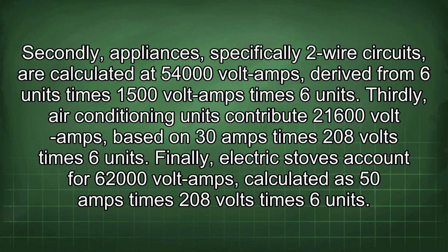Secondly, appliances, specifically two-wire circuits, are calculated at 54,000 volt amps, derived from 6 units times 1500 volt amps times 6 units. Thirdly, air conditioning units contribute 21,600 volt amps, based on 30 amps times 208 volts times 6 units. Finally, electric stoves account for 62,000 volt amps, calculated as 50 amps times 208 volts times 6 units.